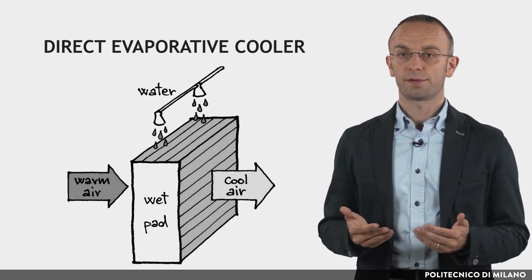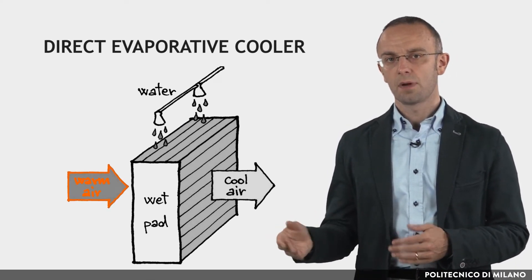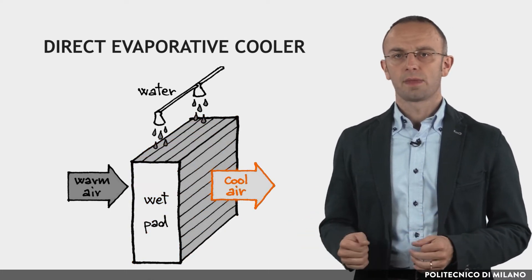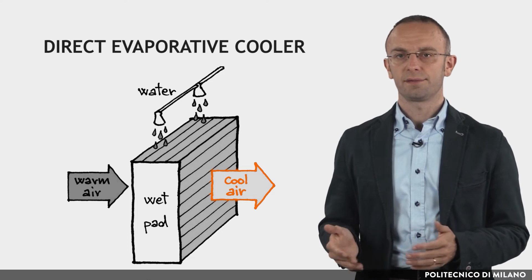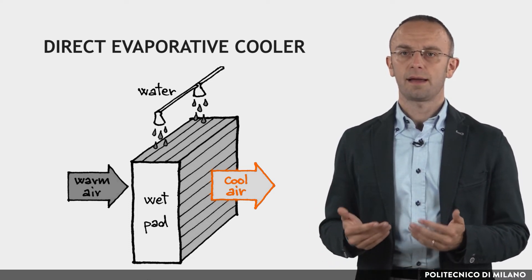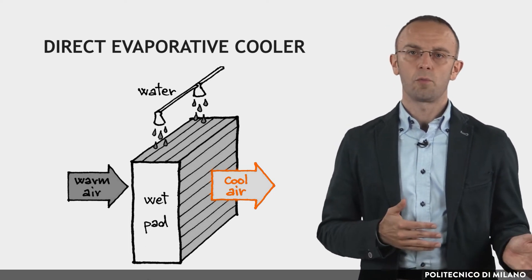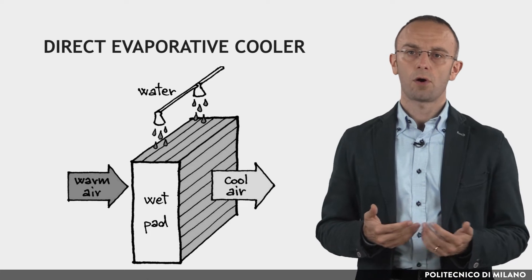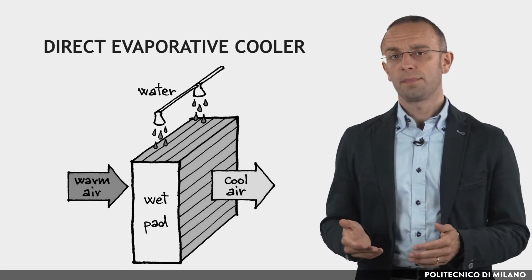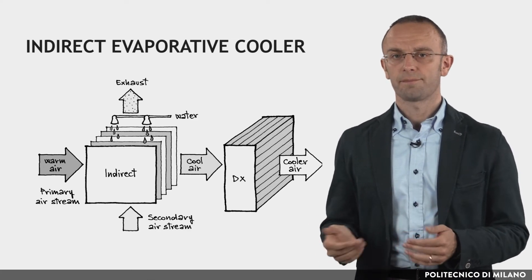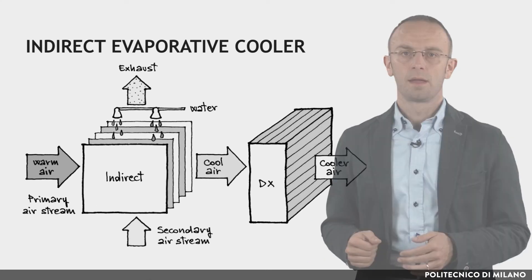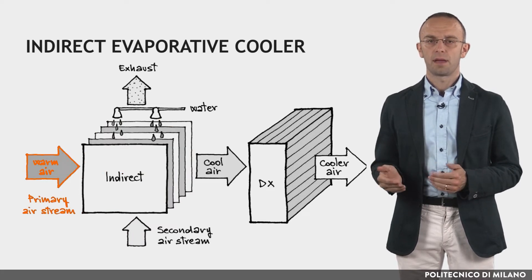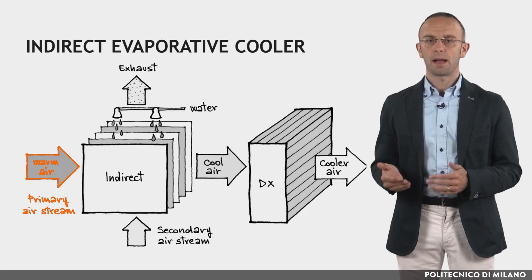In direct evaporative coolers, outside air is blown through a water-soaked medium, which is usually cellulose, and cooled by evaporation. The cooled air is circulated by a blower, cooled by 10 to 20 degrees Celsius when it crosses the water-soaked pad, and then directed into the room, pushing warmer air out through windows. However, if outdoor air humidity is not very low, indoor humidity can be too high to be comfortable. This problem can be solved with indirect evaporative coolers, where a secondary air stream is cooled by water and passes through a heat exchanger to cool the primary air stream, without adding moisture to it.